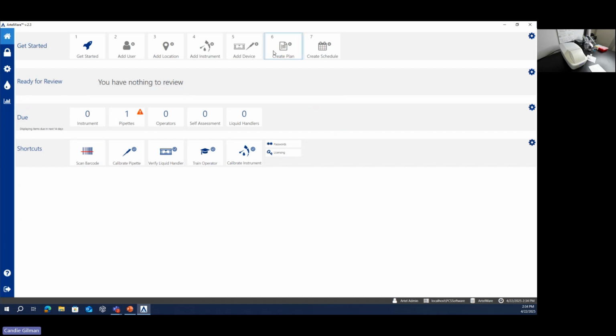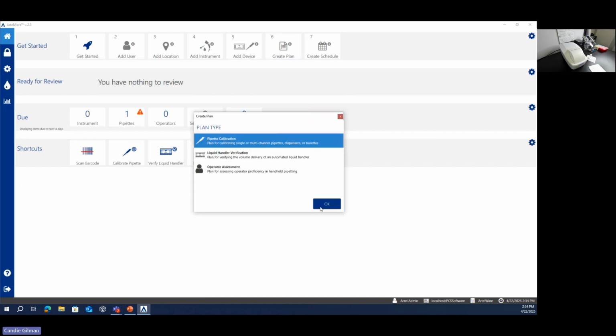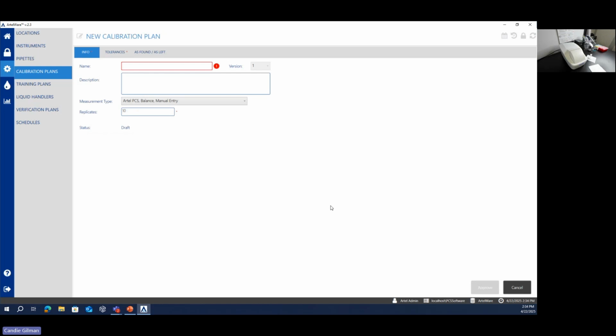And now I need to create a plan for this pipette calibration. So the plan is where I tell the system what are the volumes that I'm testing, what are pass or fail, and how many replicates am I taking as well. So I'm going to call this plan April 25th. And this is a 20 microliter variable pipette. And I'm only going to be testing it at 10 and 20 microliters.